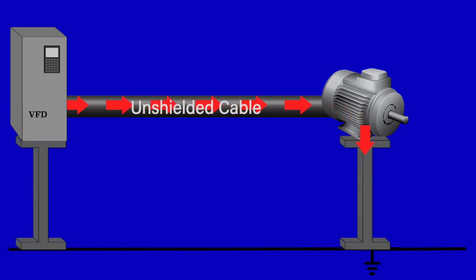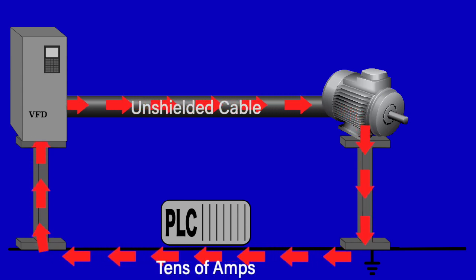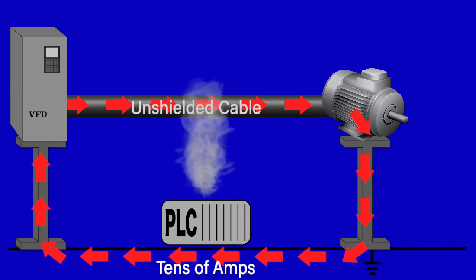This current can travel through the motor frame and base plate and through building steel back to the inverter, potentially creating operational problems for any control or communication devices along its path. Tens of amps flowing on the ground next to one of these devices can cause intermittent issues with the device or outright failure.